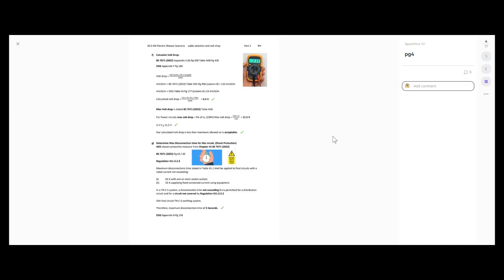In the regs, table 4AB, it gives us a table to determine the maximum volt drop. When we've got a supply from the public supply network — the DNO, which is what this scenario is — we're allowed a maximum of 3% of our nominal voltage for lighting, or 5% for anything else such as power. So in this case we're allowed a maximum of 5%. 5% of 230 is 11.5 volts. We've got a calculated volt drop of 3.3, which is less than 11.5. So the cable is good for current carrying capacity and also good for volt drop. 16mm is good to go.